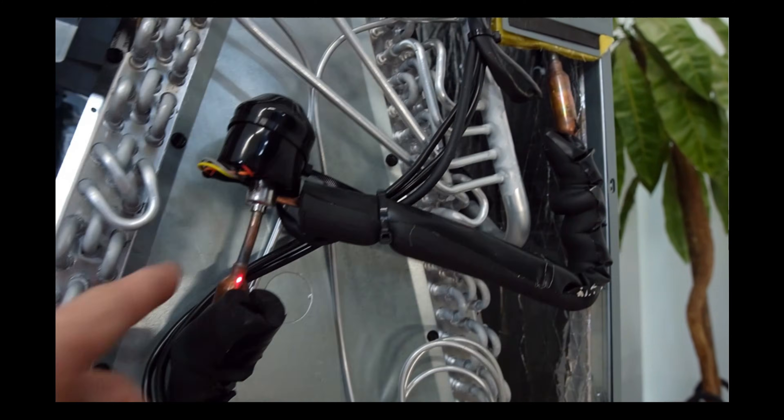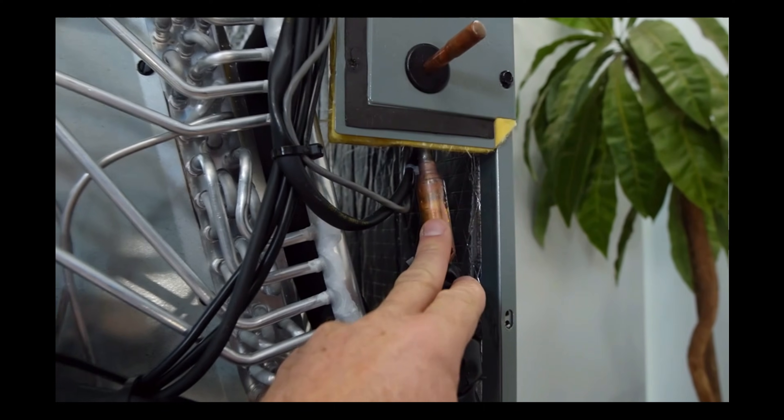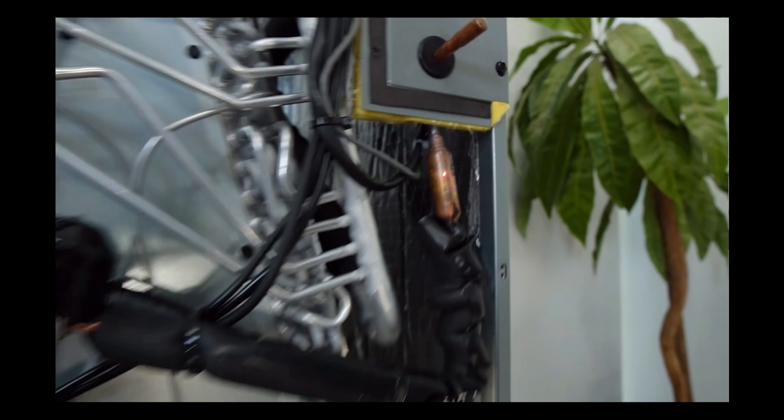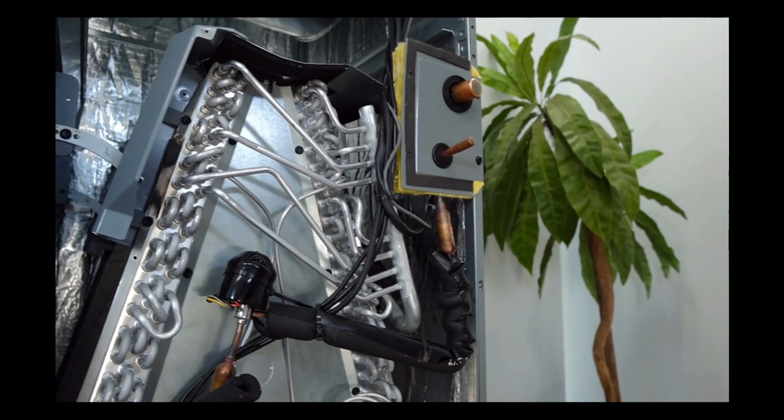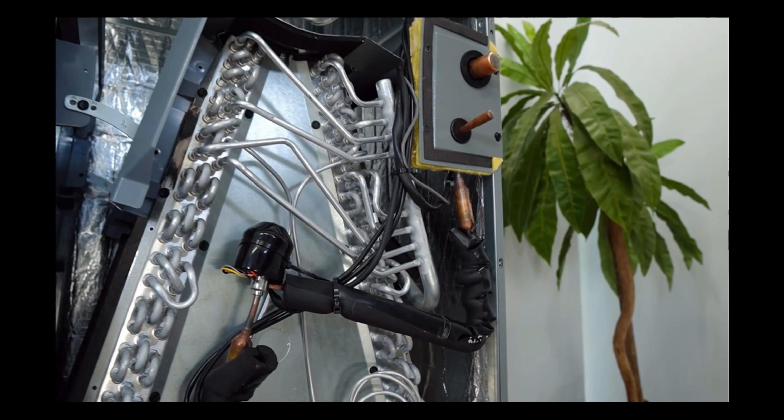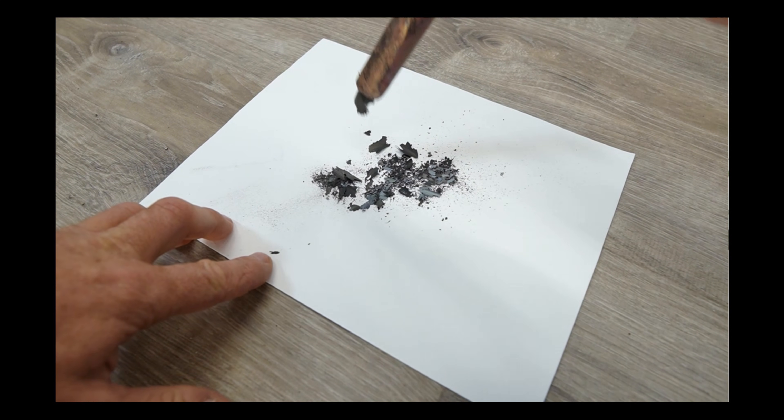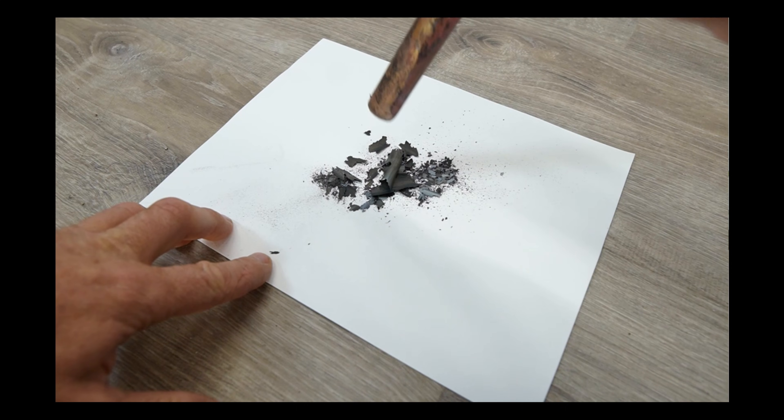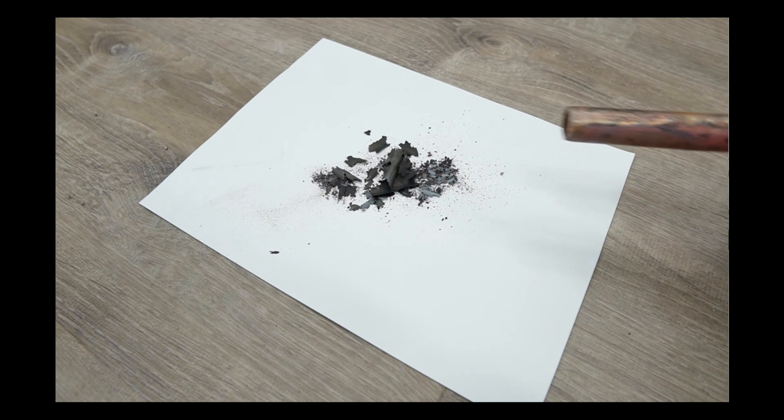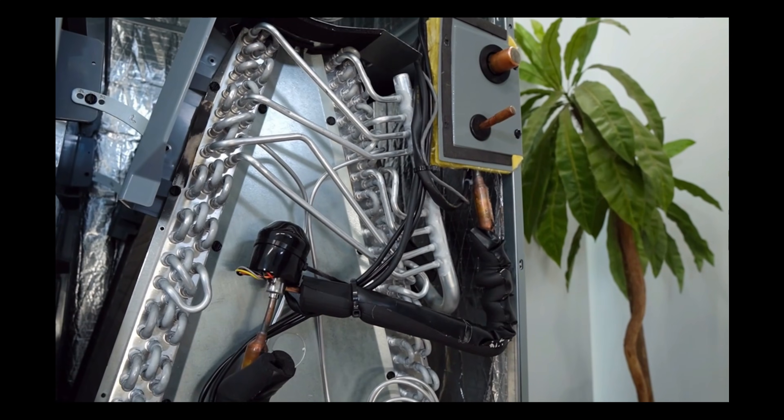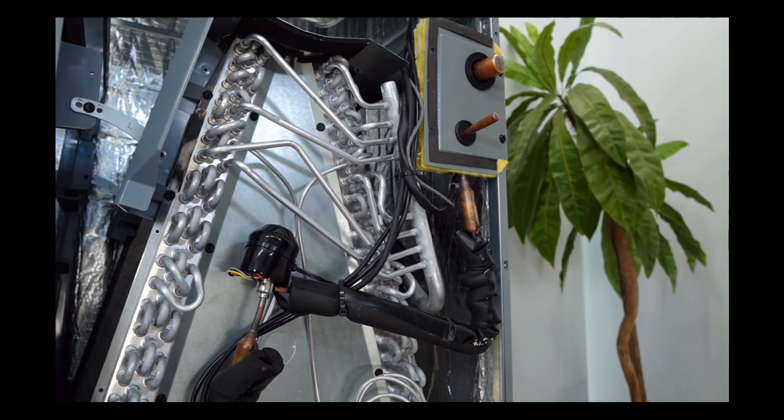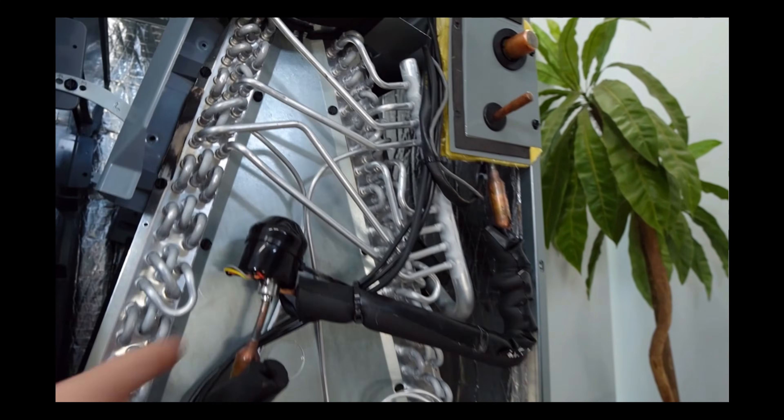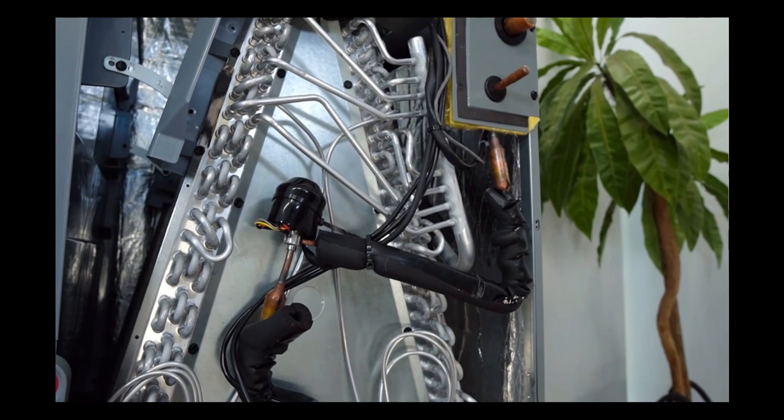As we explained in the last Daikin Fit video, the coil has two super small strainers as you can clearly see them right there. Never, by any means, never ever braze these units without using nitrogen. Look at the oxide that came out of the lines that have been brazed without nitrogen. This oxide can clog these tiny strainers and limit the system performance.